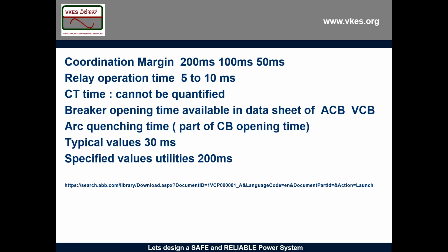So this coordination margin is fixed irrespective of the type of earthing that you provide? No, sir. Coordination margin is fixed for a project. Let's say you're doing a project for Shell, particularly for this site in Nigeria, and they have all ABB breakers. Okay, you fix this margin. Now you are doing one more project where you have some old GE breaker, then you please increase the coordination margin. So as a relay engineer, for one plant, don't keep changing the coordination margin.